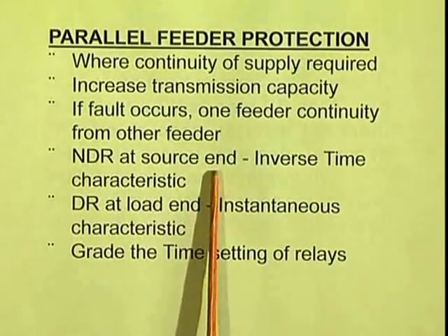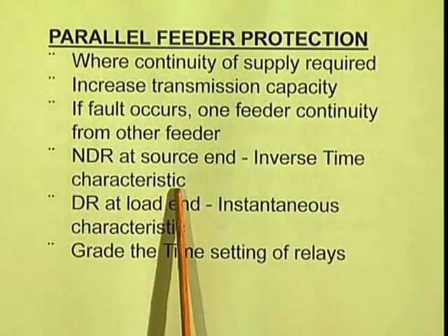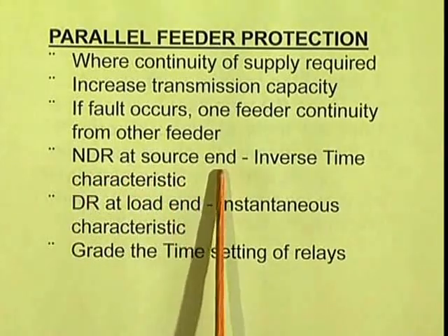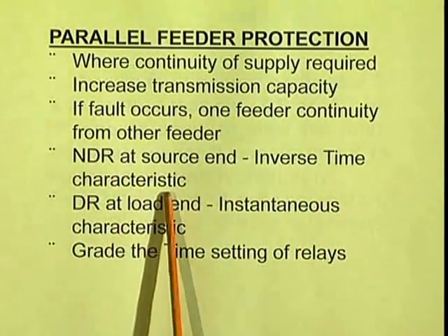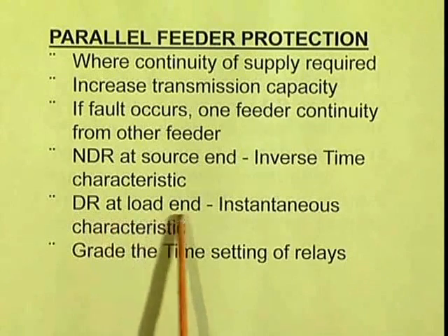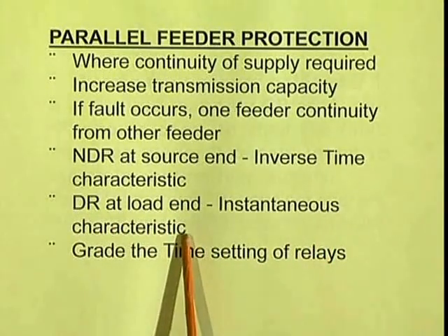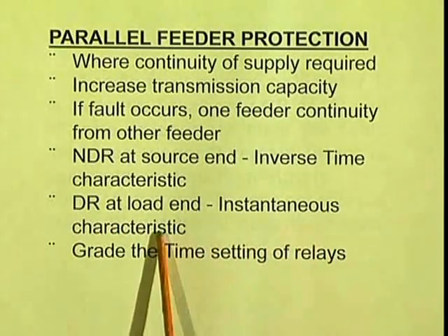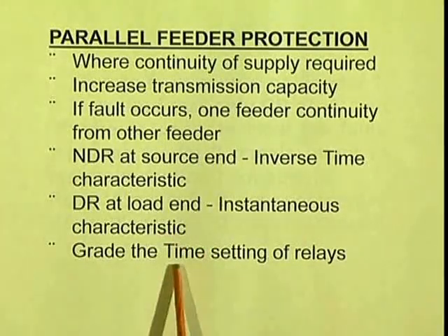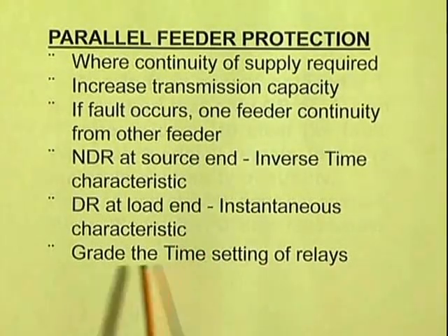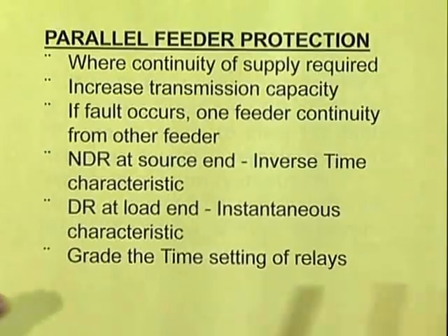Non-directional relays at the source end, with inverse time characteristics. Directional relays at the load end, but they have instantaneous characteristics. That means here the relay will operate instantaneously. Grade the time setting of relays. So, the non-directional relay will have a graded time setting.